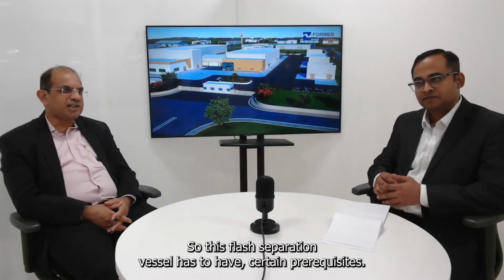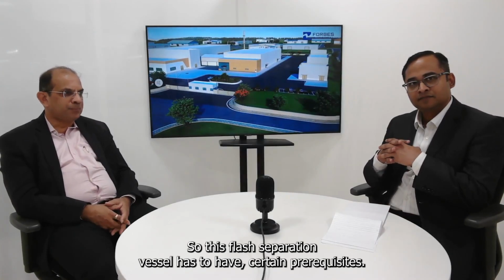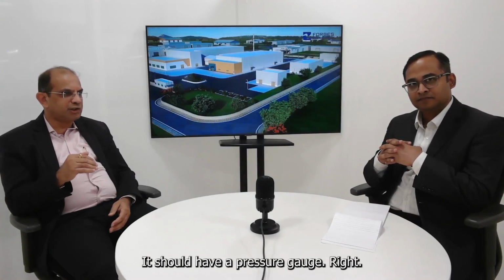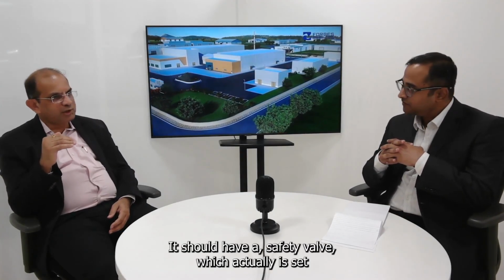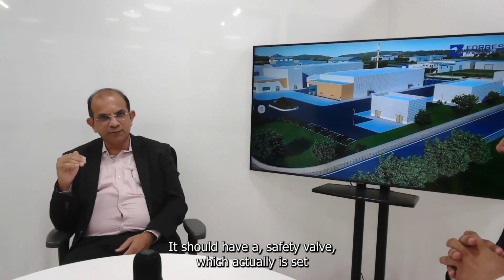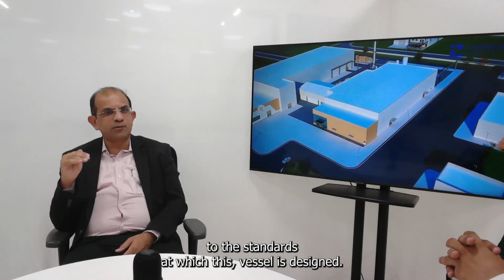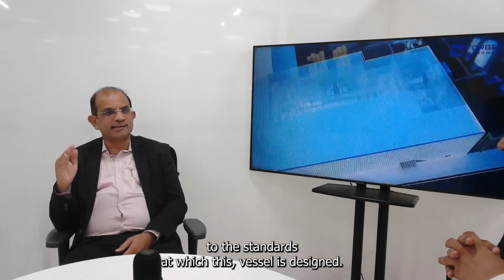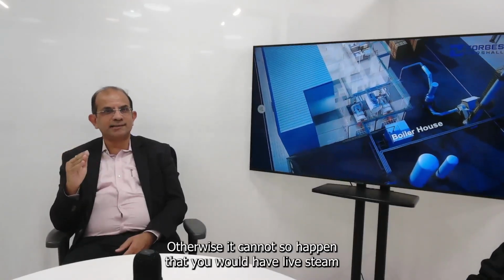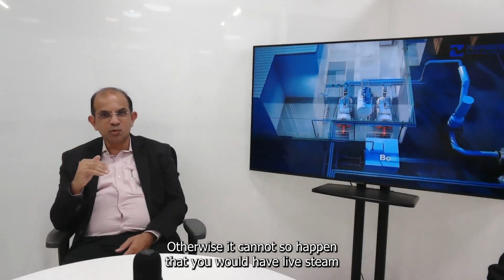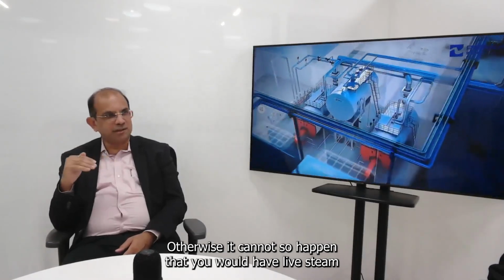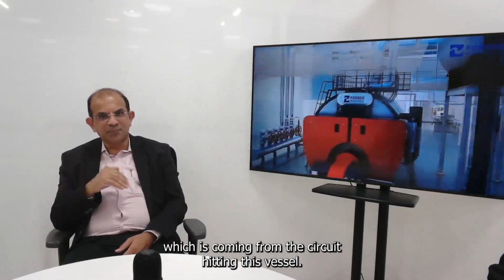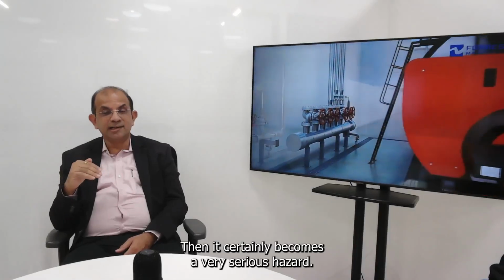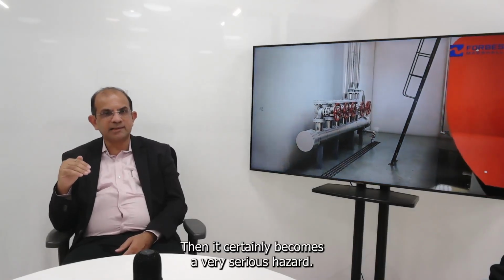So this flash separation vessel has to have certain prerequisites. It should have a pressure gauge. It should have a safety valve, which is set to the standards at which this vessel is designed. Otherwise, it could so happen that you would have live steam coming from the circuit hitting this vessel. Then it certainly becomes a very serious hazard.